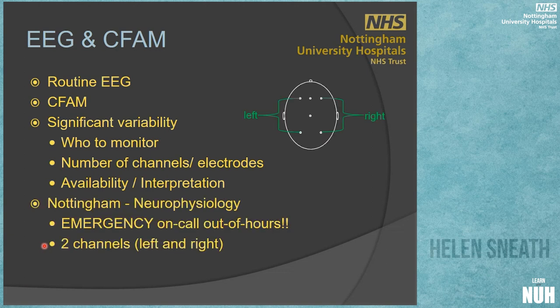In Nottingham we do this as an emergency on-call out of hours. The two channels are just from the left and right side of the head. If you look at this diagram - a picture of the head from above with the nose at the front and ears either side - these dots are where we've got our electrodes placed. We're recording a wide-spaced montage on the left and wide-spaced on the right. It's a simplified version of an EEG.